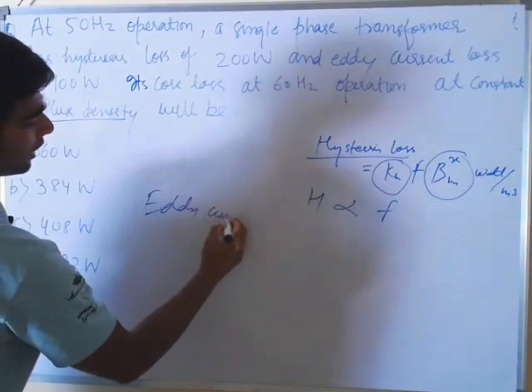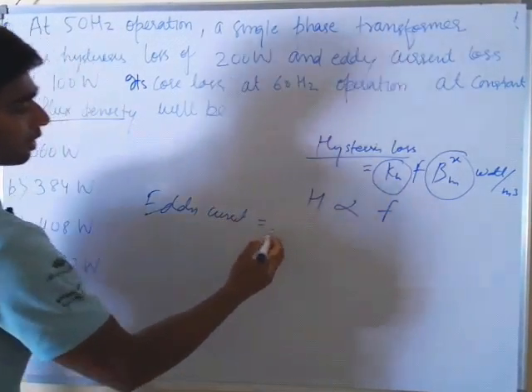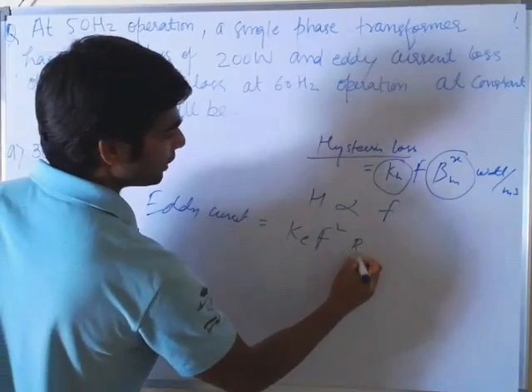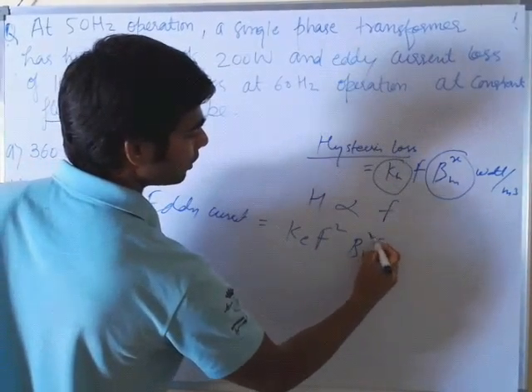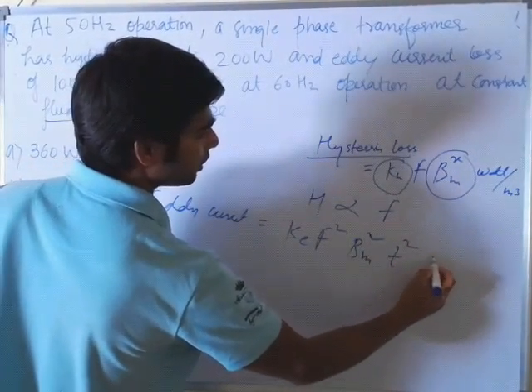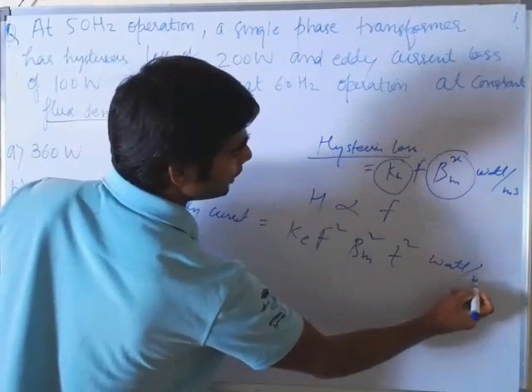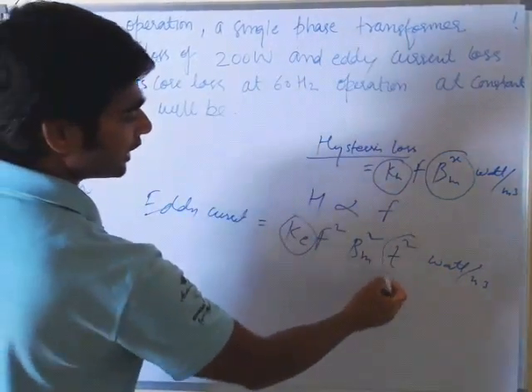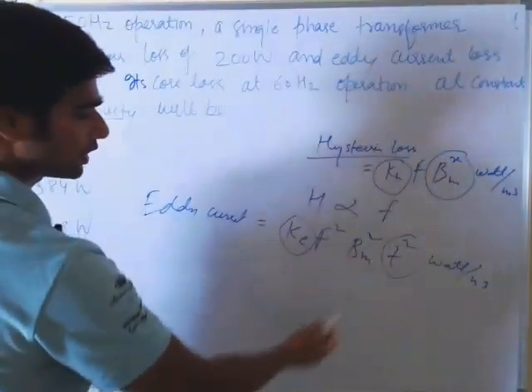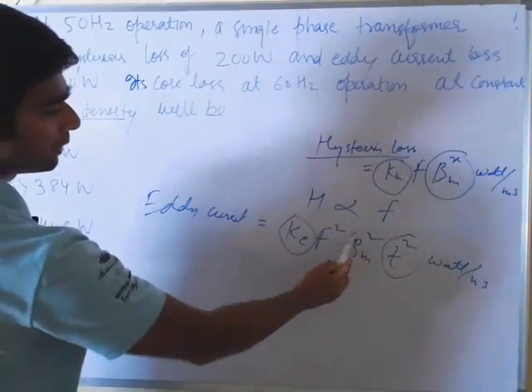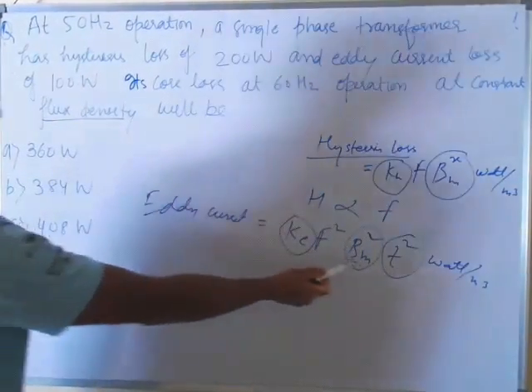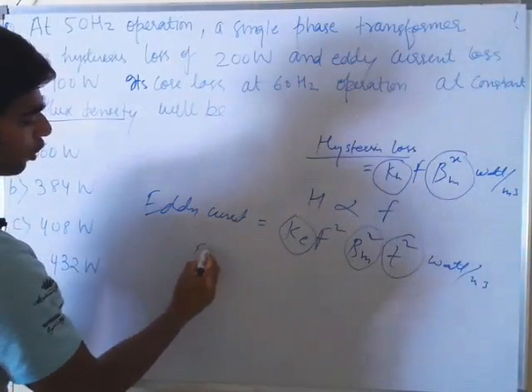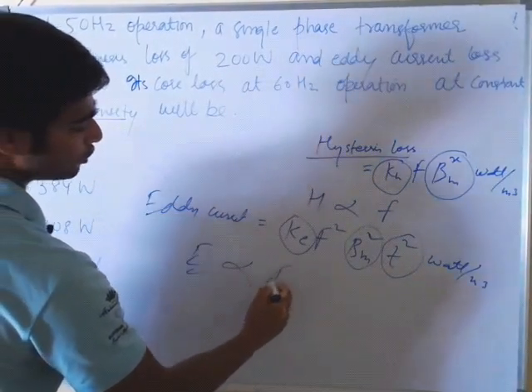Now for eddy current loss, the expression is KE × f² × BM² × T², in watt per meter cube. KE is constant, T (thickness of core) is also constant, and BM is already mentioned as constant in the question. So eddy current loss is proportional to f².